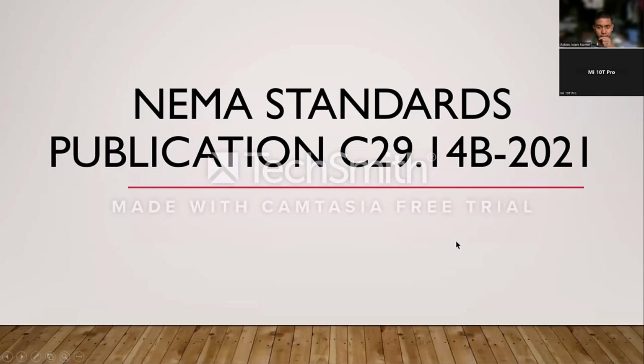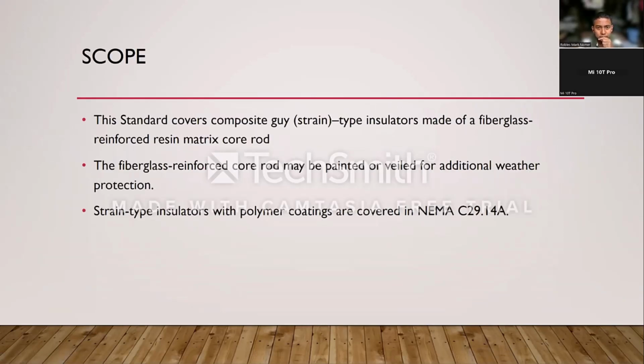NEMA Standards Publication C29.14b 2021. Scope. This standard covers composite guy strain type insulators made of a fiberglass reinforced resin matrix core rod. The fiberglass reinforced core rod may be painted or veiled for additional weather protection. So, bale, dito, may kulay at cover siya in order para sa weatherproof. Strain type insulators with polymer coatings are covered in NEMA. So, bali nakasakop sa NEMA yung lahat ng insulator polymer dito.